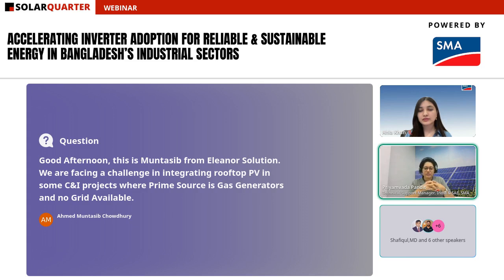For these kinds of projects, this hybrid controller is not a standard off-the-shelf product like a typical on-grid inverter. It would be customized according to your project requirements. Often a bit more data is required, about your generators and controllers, and also about your typical load pattern. Accordingly, we can suggest the right size for your PV plant and how the PV diesel hybrid controller would be configured for your project. So there's a bit more technical due diligence, or engineering support, that we would provide for these kinds of projects.